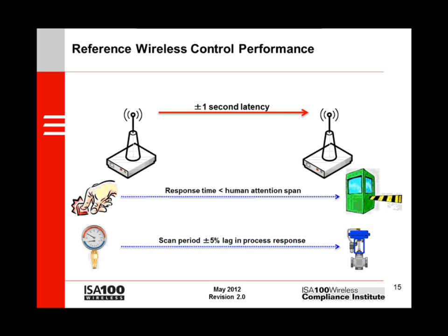On this slide, we suggest that something on the order of one-second latency end-to-end should be the basic performance reference for controls. Some applications can manage with less performance, and a few may need more. But we have found that one-second latency covers a reasonable range of applications without involving painful user trade-offs. For example, consider a human-in-the-loop control application, shown here as a person pressing a button. Normally, users want to see some feedback from their actions. It is well known that when a response time exceeds about two seconds, the user's attention will start to drift. So, we suggest one to two seconds end-to-end as a reasonable target for human-in-the-loop control.